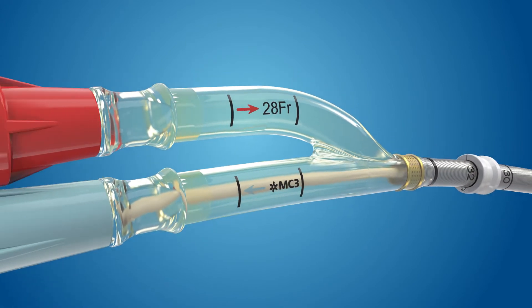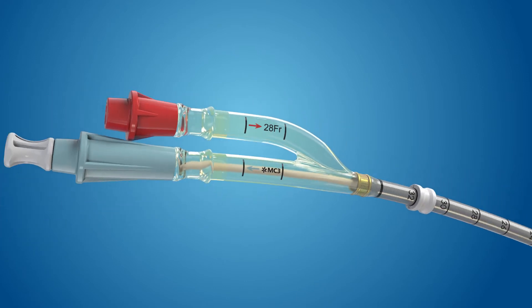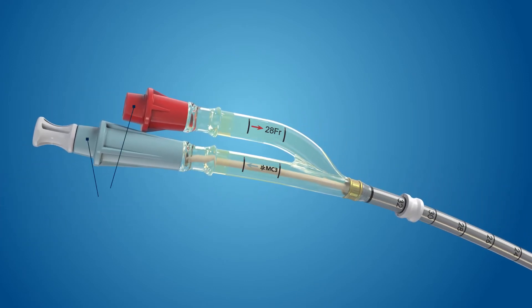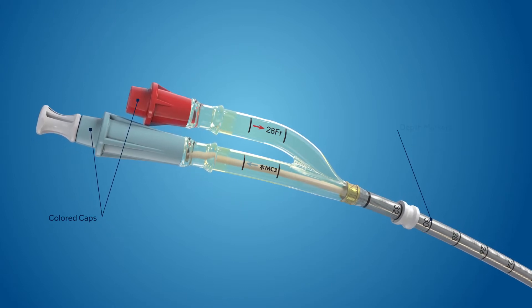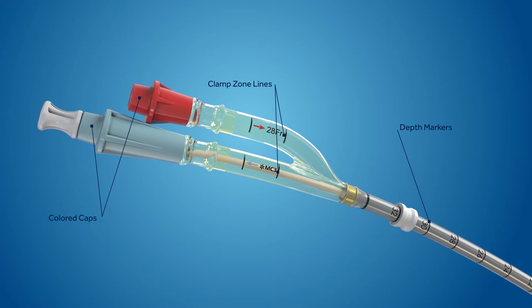The Crescent catheter has features to aid in use and handling, including colored caps that indicate the infusion versus drainage lumen, depth markers, and identifiable clamp zones.